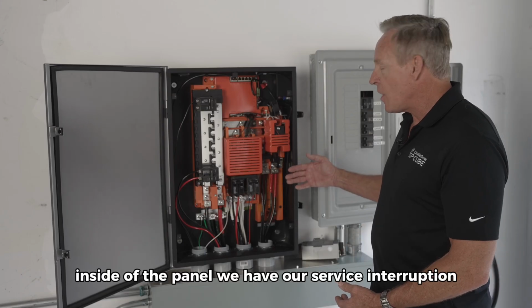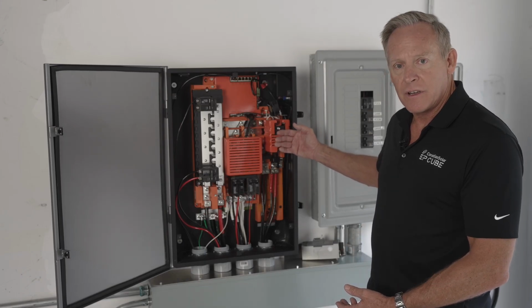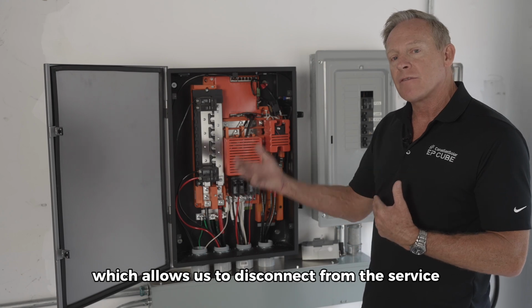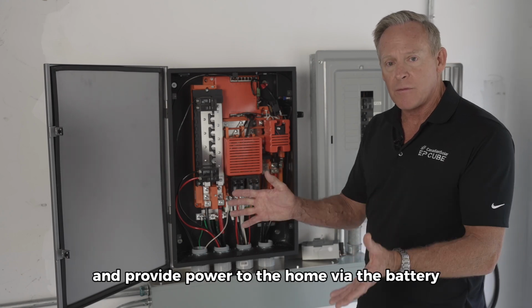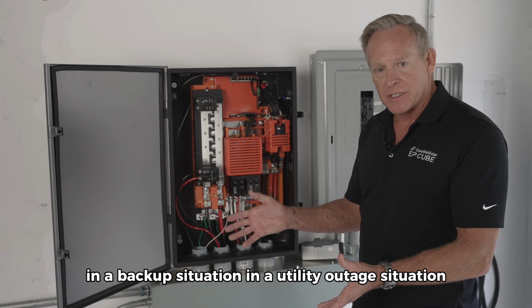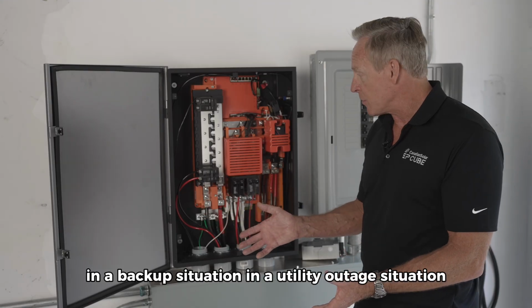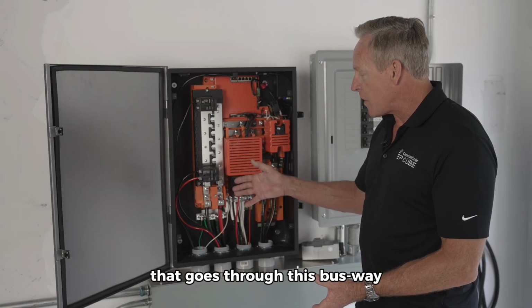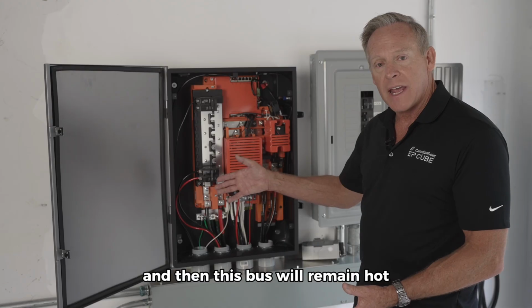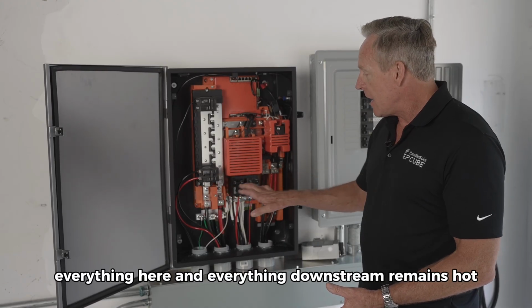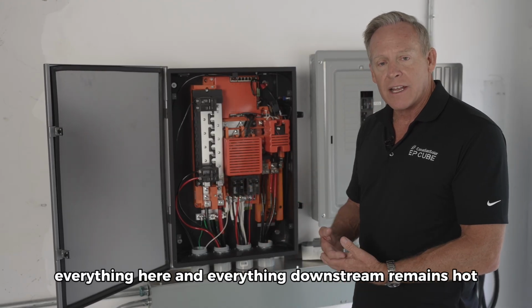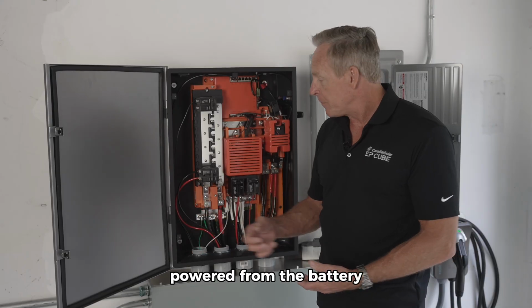Inside the panel, we have our service interruption, which allows us to disconnect from the service and provide power to the home via the battery in a backup situation, in a utility outage situation. That goes through this busway, and then this bus will remain hot. Everything here and everything downstream remains hot, powered from the battery.